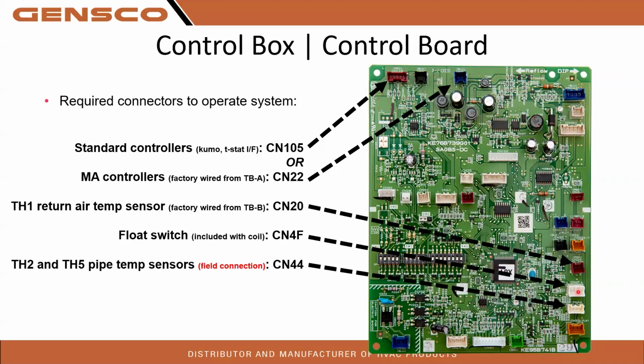CN4F, this one will be field connected. So this is for your condensate safety switch, that CN4F with the pigtail that it comes with. That pigtail is going to plug into right here. CN4F, that's for your float switch. So that if that thing ends up open, it is going to give you a condensate error. So it has to have the switch in there. If for whatever reason you choose not to use any of the safety switches tied into the coil, take that pigtail connector and wire nut it together. That way it has something closed on there. Otherwise it will not run.